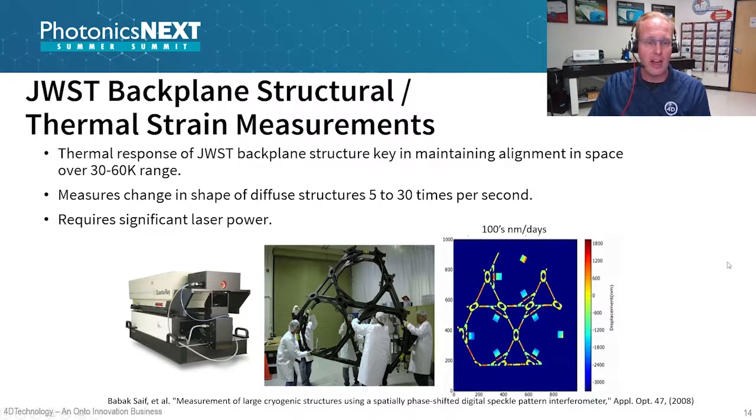that varied over time. And again, with the dynamic interferometry, they were able to measure that shape and change, from 5 to maybe even 30 times per second, to really get an idea of how things fluctuate over time, and that allowed them to optimize design, correct things to make better uniformity, and other variations and corrections of that nature.